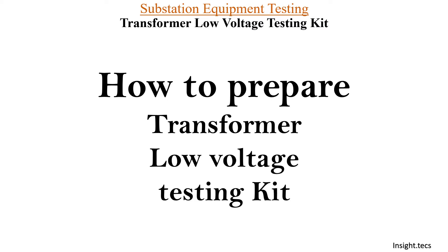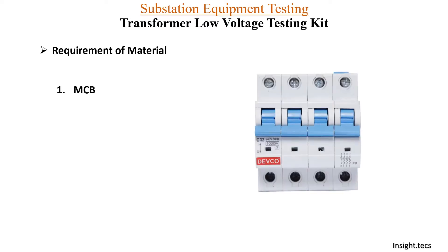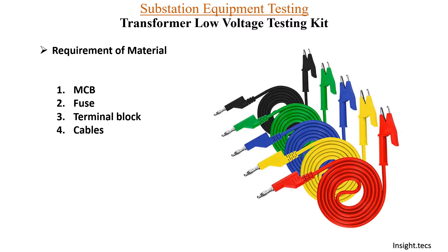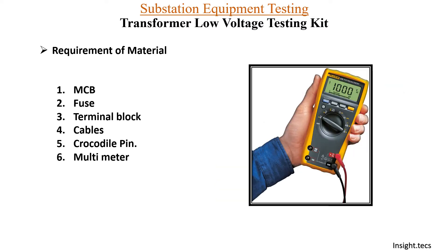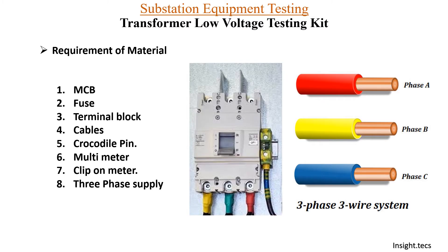Now, how to prepare a transformer low voltage testing kit by yourself? The material requirements for making a low voltage transformer kit are: first is MCB, second is fuse, third is terminal block, fourth is cable, fifth is crocodile pins to be connected at HV and LV terminals, and next is multimeter and clip-on meter. If you have all this material, you can prepare the low voltage testing kit yourself, and you will require a three-phase supply for its operation.